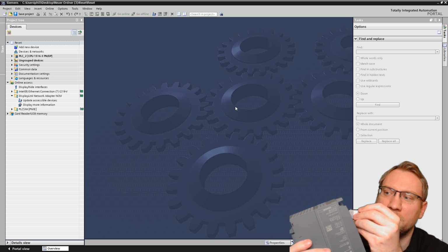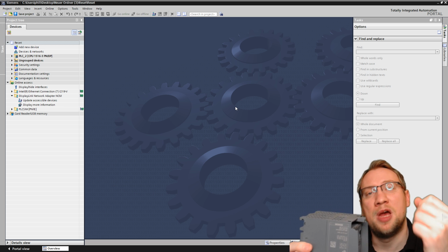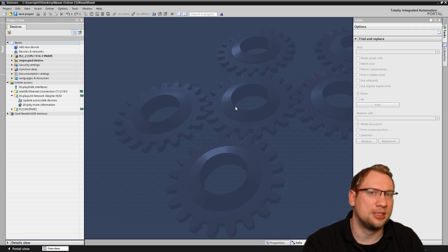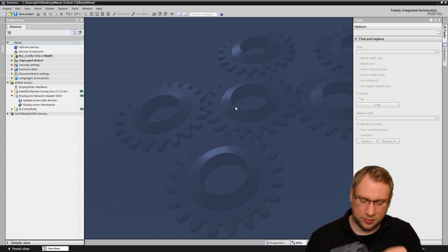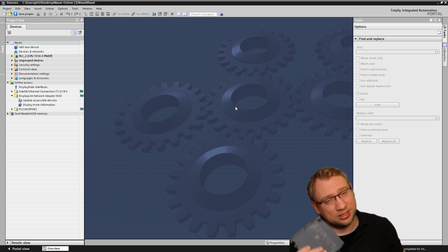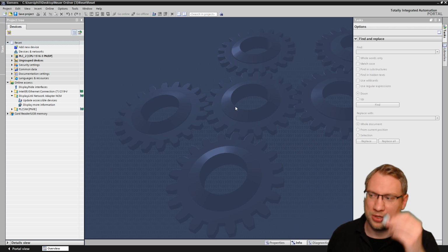If I have the memory card, it is just a memory reset, meaning just my data is gone. I'm just resetting all the data. I'm not losing anything. If I take it out, boom, resetting it. Everything is lost that's on here. I still have the program on the card though.